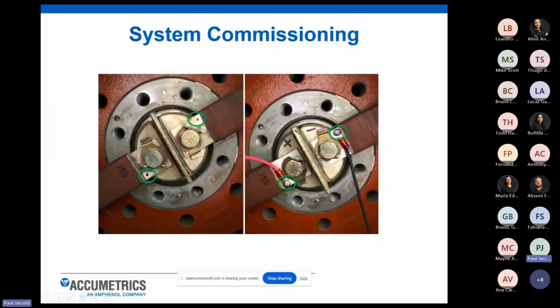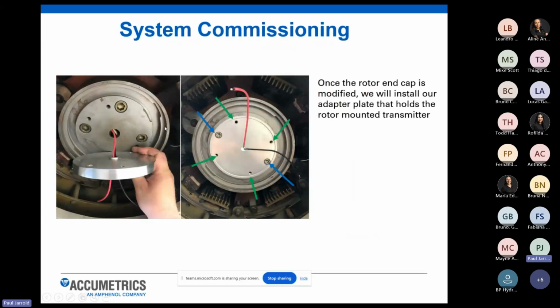So there is your field windings that go down through the center of the brushless exciter shaft into the generator shaft, and then get wrapped around the generator rotor in many turns of copper bus bars. There we drill and tap two small holes directly into the bus bars themselves, and we connect our plus and minus field voltage contacts on those bus bars. Then those wires get routed up through that center hole in the rotor end cap.